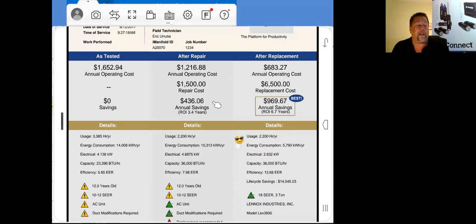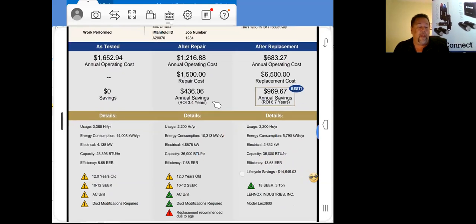And here's the details - you dropped your usage, energy consumption, there's your electrical, the capacity - they're going to be much more comfortable. As you can see, the capacity is 36,000 from when you started off; that capacity when we did the test-in was 23,396 BTUs. Our efficiency, we've got an EER rating of 13.68, and nothing but green here.